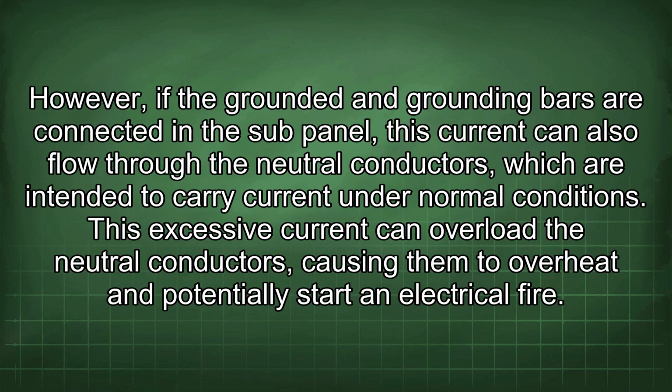However, if the grounded and grounding bars are connected in the subpanel, this current can also flow through the neutral conductors, which are intended to carry current under normal conditions. This excessive current can overload the neutral conductors, causing them to overheat and potentially start an electrical fire.